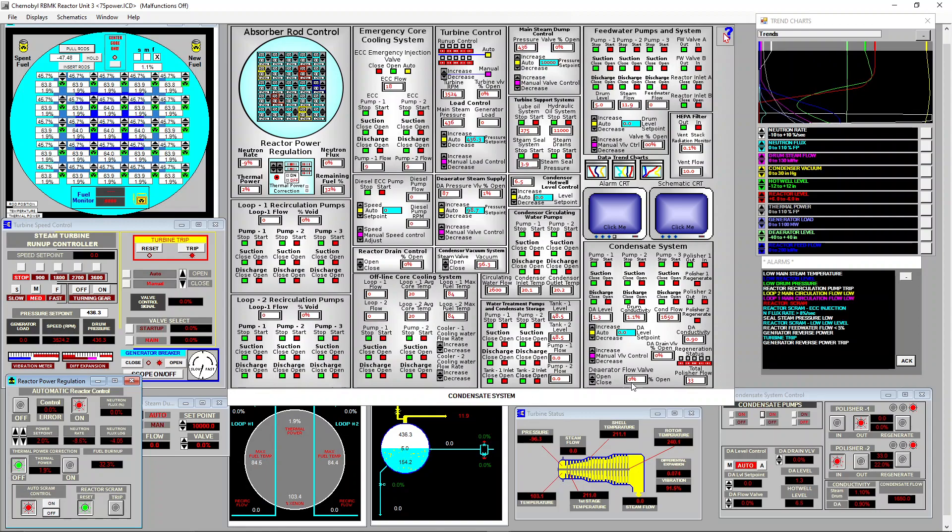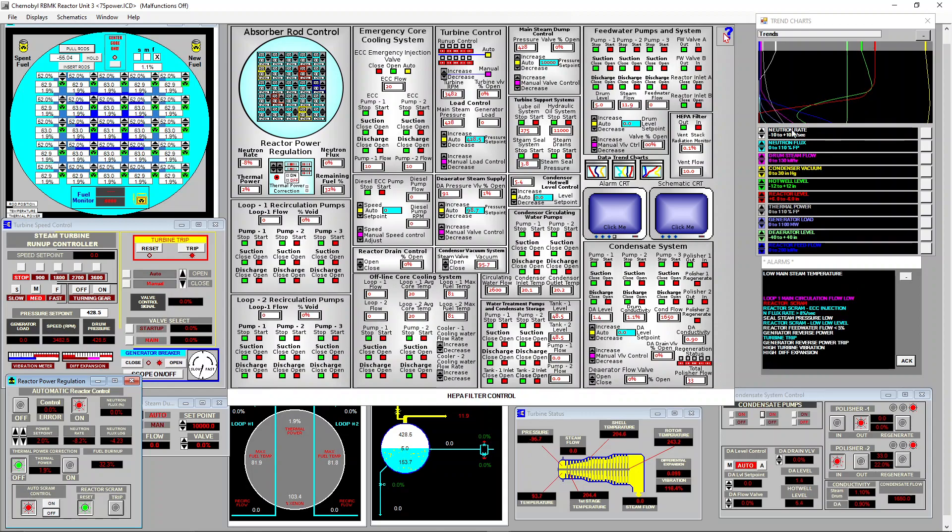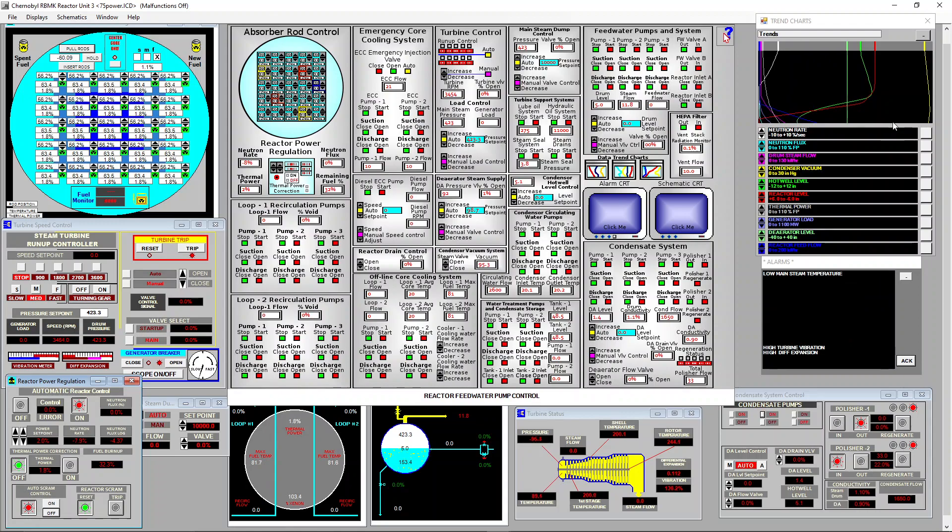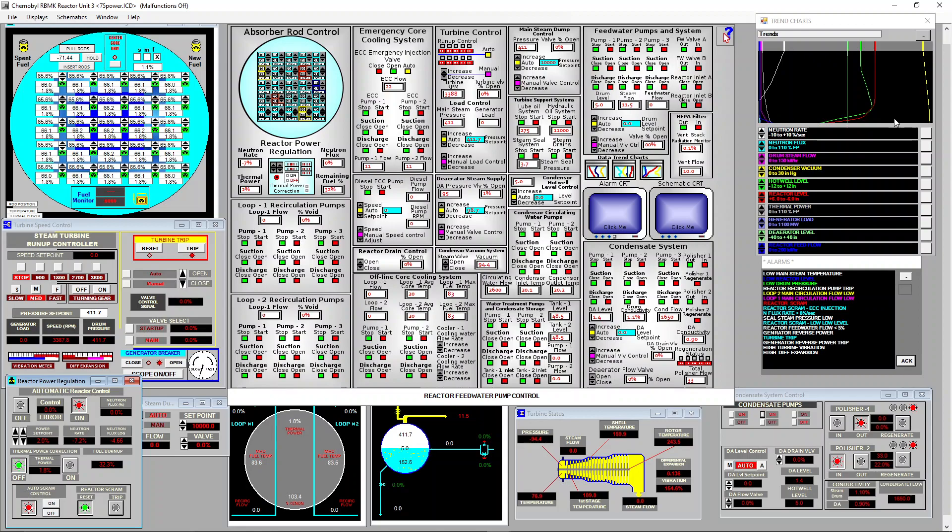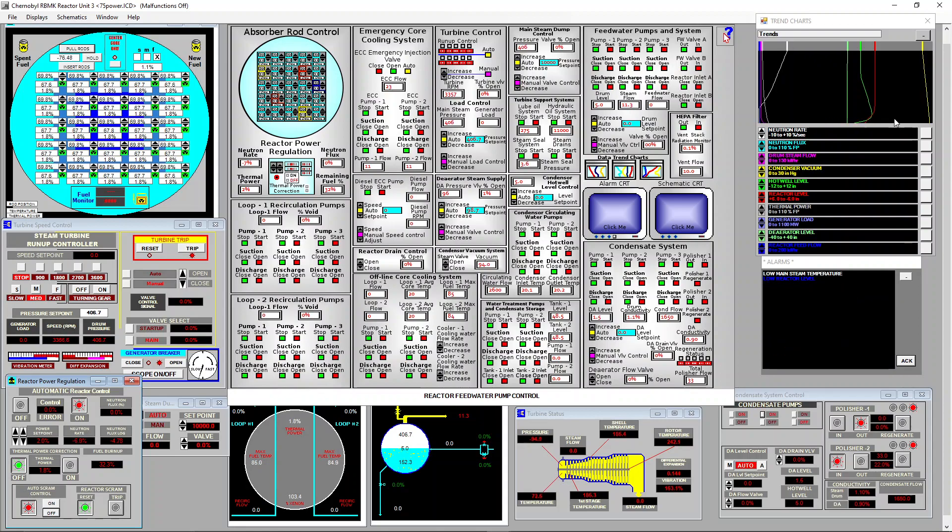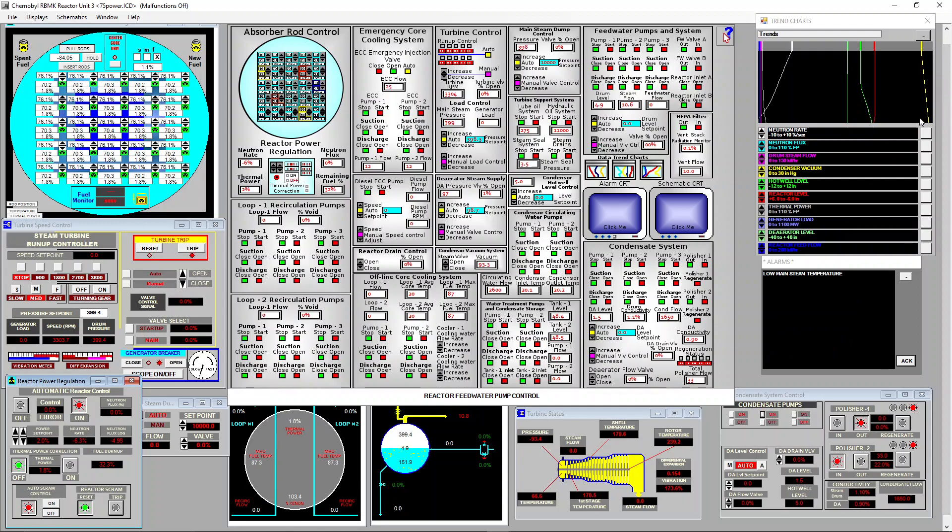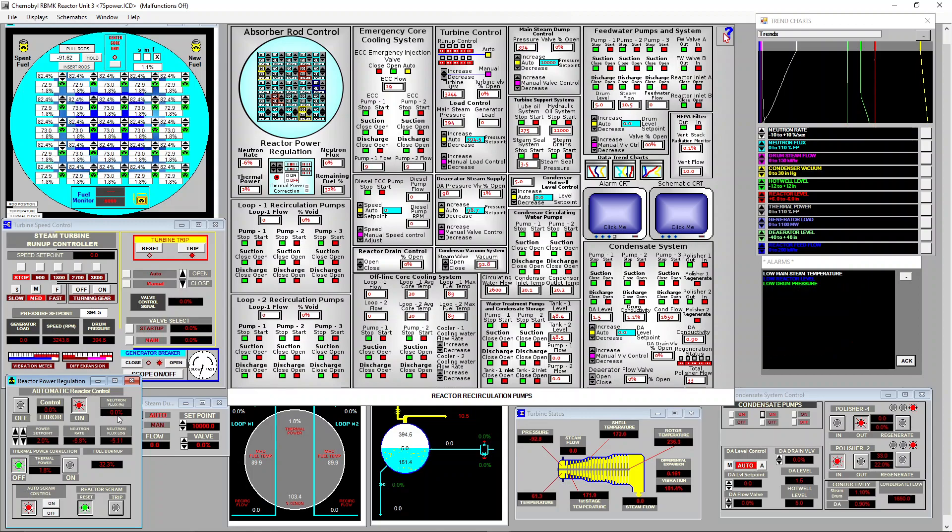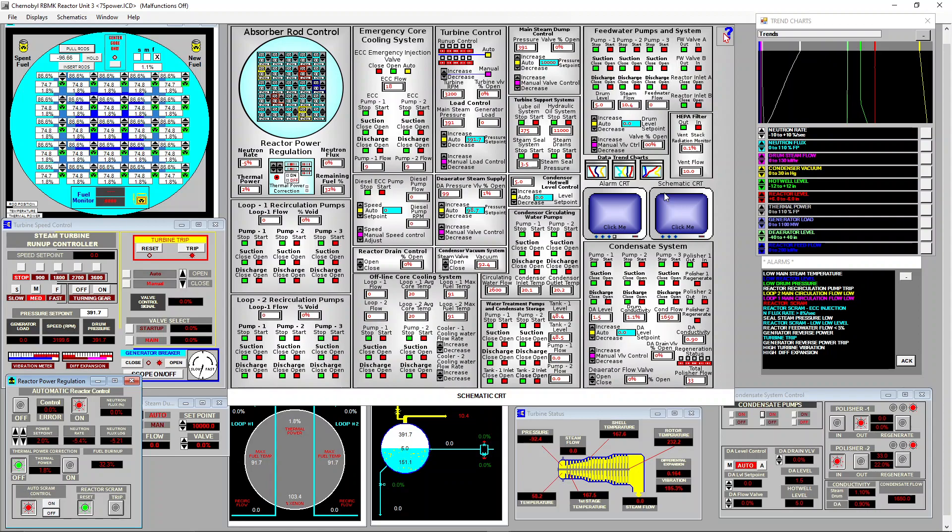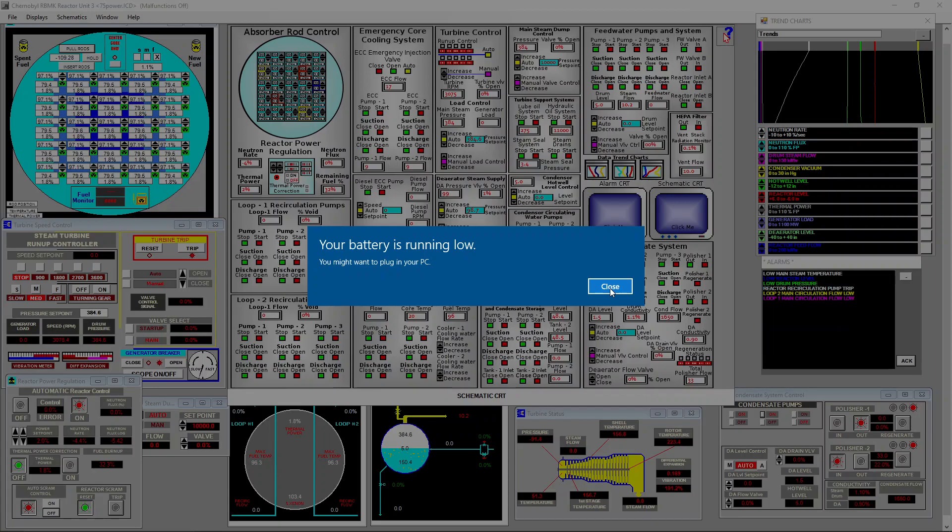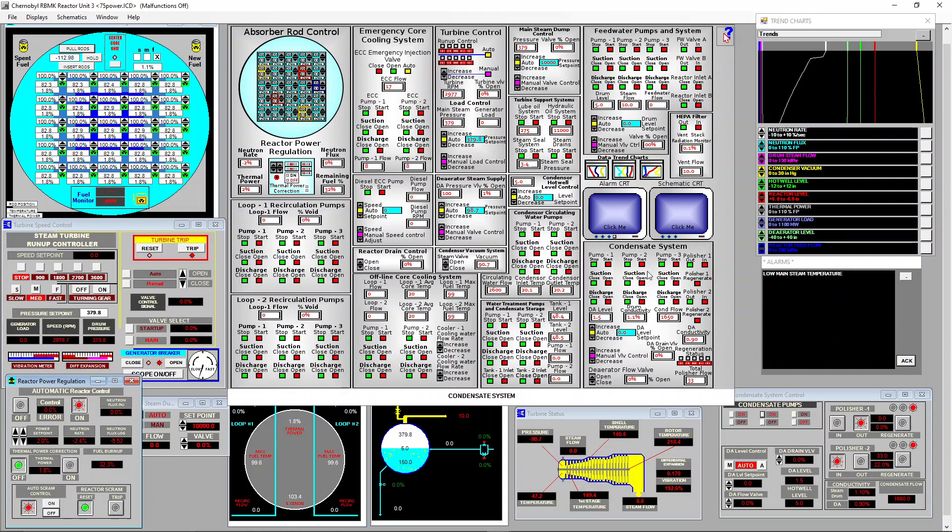What happens is the reactor lost controllability trying to catch up the control of the reaction. It just started withdrawing rods but it was already at the position of four percent of insertion, so withdrawing at this point didn't make much of an effect. I didn't see it but probably because the turbine tripped or some auxiliary tripped we had a reactor scram, and the reactor scram caused the surge. This is the very thing that caused the accident at Chernobyl 1986. Because we were so low in reactivity the surge could not bring the reactor up to a critical runaway and to an explosion, but you really saw the neutron rate going super high like to plus infinite or at least out of scale. The neutron flux went up I did not see the number, you can rewind the video, but I think it went up like five or ten percent. When the boron started to effectively decrease reactivity we saw the effective decrease of neutron flux.